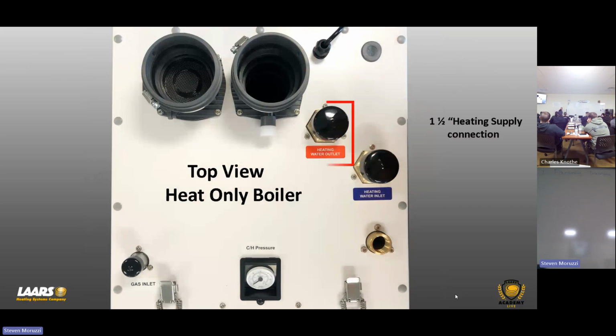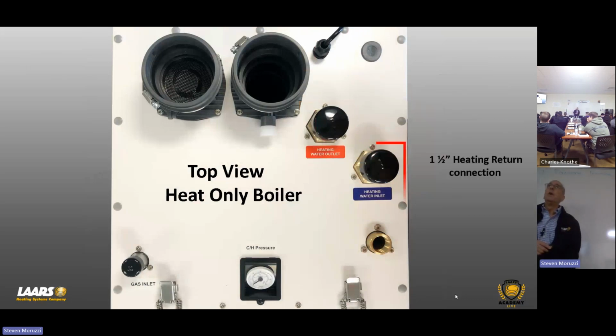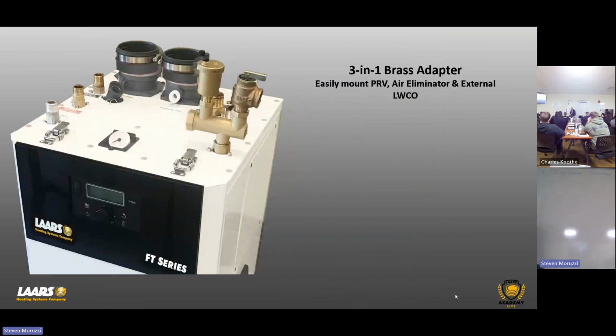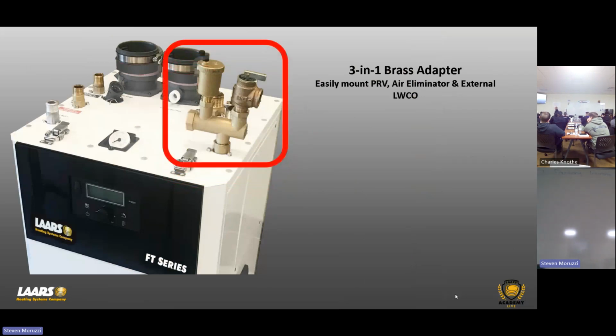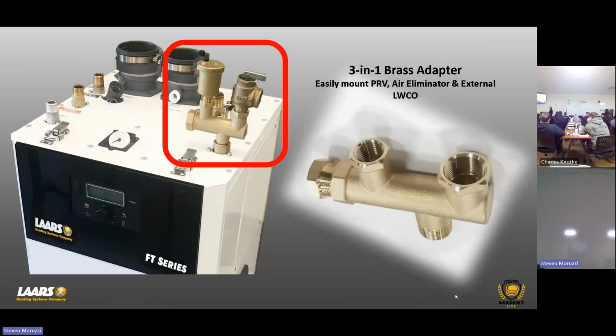We have 1.5-inch heating supply connections and 1.5-inch return connections. And right here, we're going to refer to this as a 3-in-1 brass adapter. Keep in mind, we need the relief valve and the vent, right? So we give you this all in the bag or all in the box.